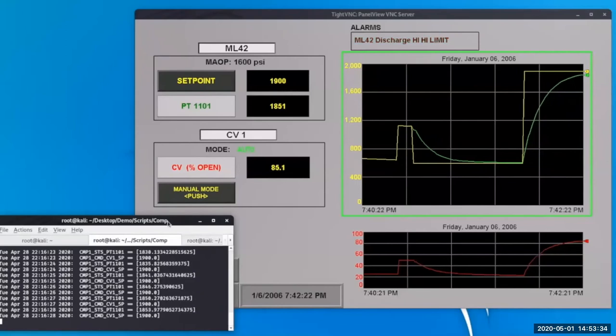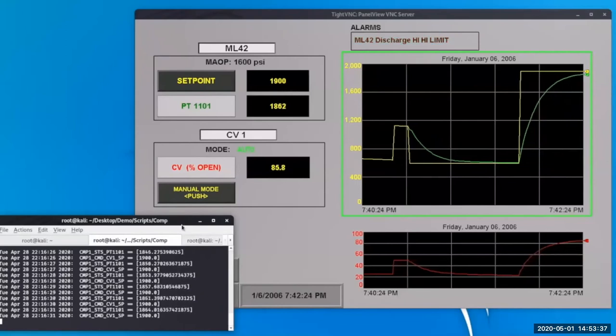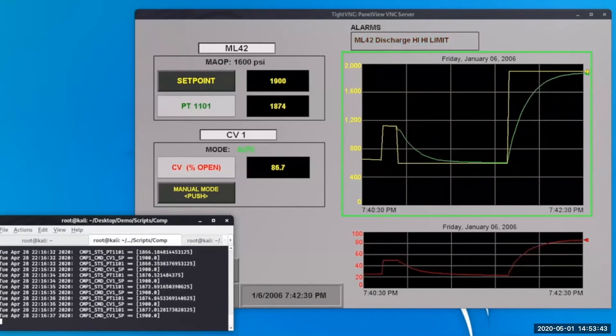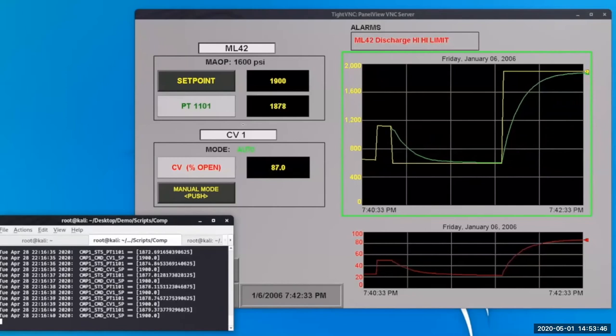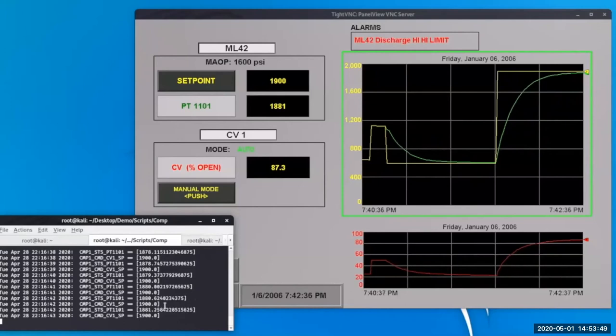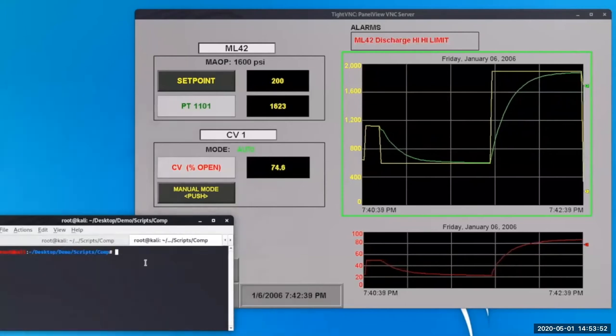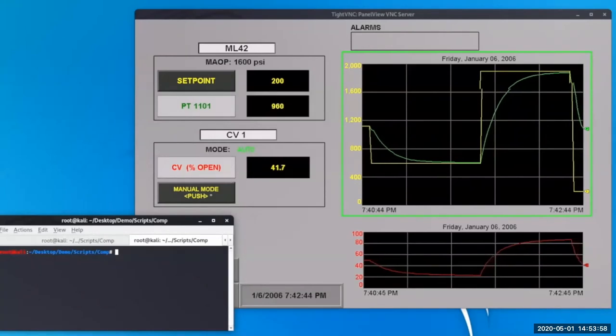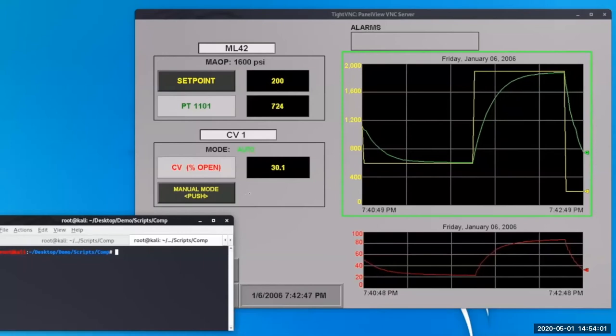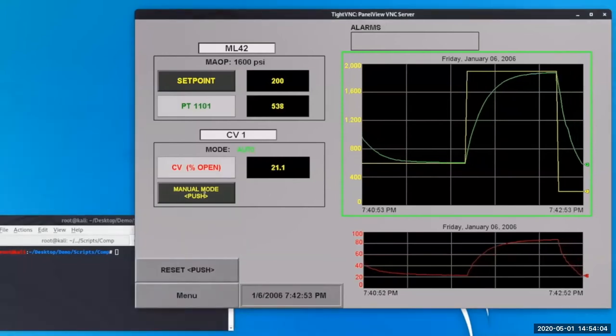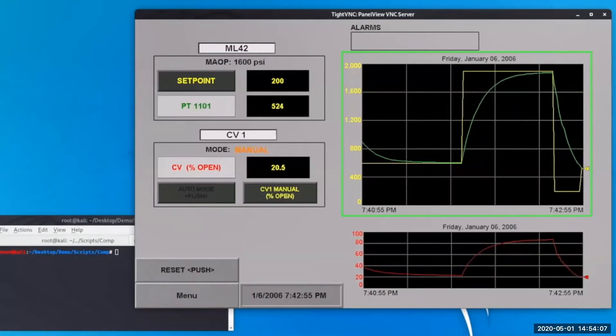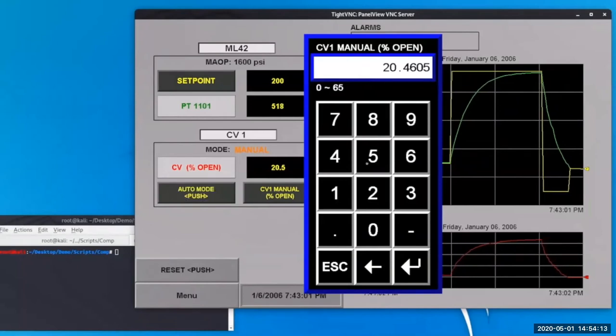The set point value in the HMI button is controlled by the HMI, not by the PLC. You could potentially put logic in the PLC to sanitize those inputs. However, that is something that has to happen in certain scenarios and is an extra function required during the engineering and deployment of these systems. In the next example, if we bypass the HMI to manipulate the control valve, we have to first disable auto mode by enabling manual mode, then open the numeric entry window and provide a value for the control valve position.